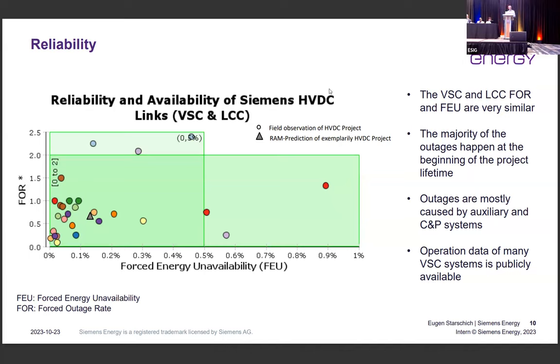The other one is the forced energy unavailability, saying if it fails, how long does it take to restart it, or how long does it take to repair the fault? So these are the two key numbers. We want to say how often does it fail, and if it fails, how much time does it take to restart the system. These key numbers are shown here in the green.